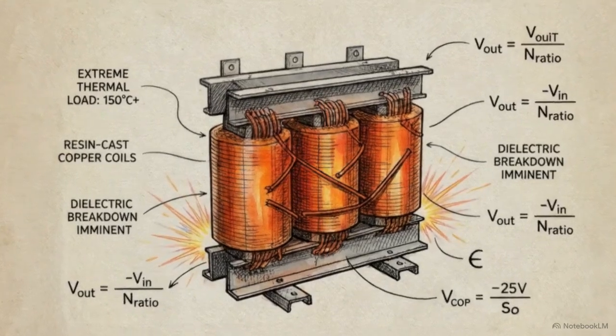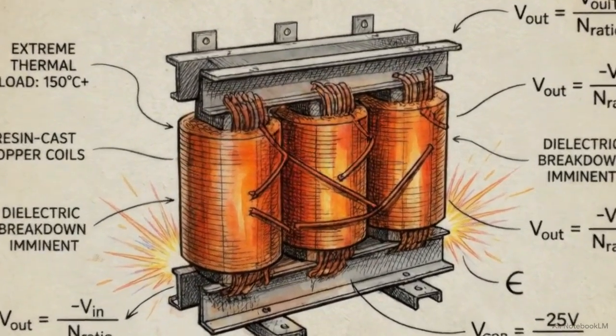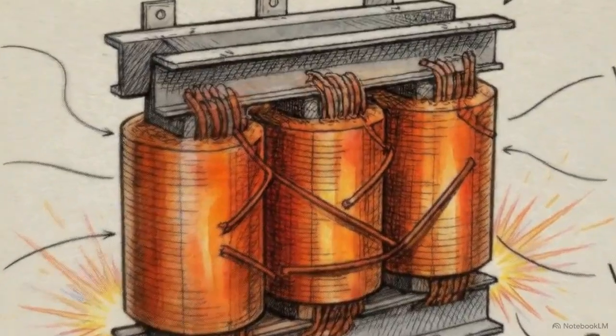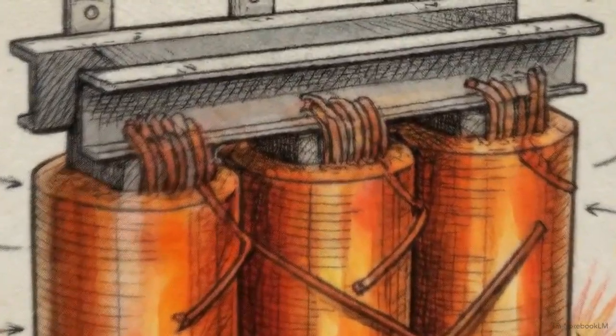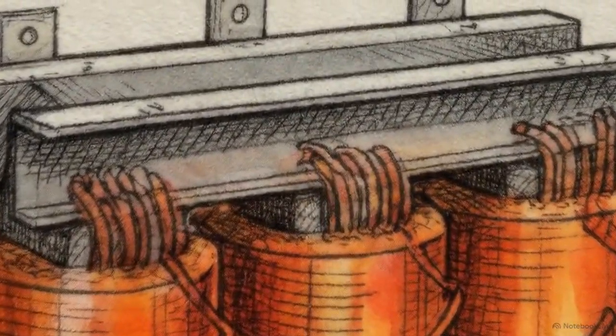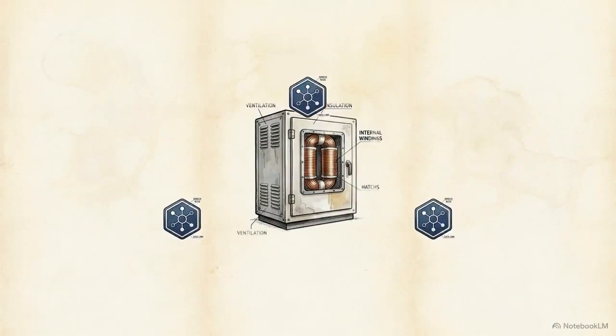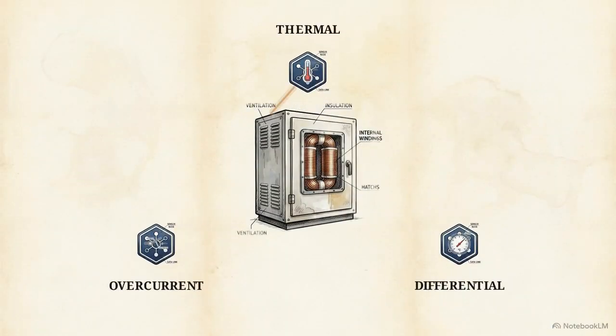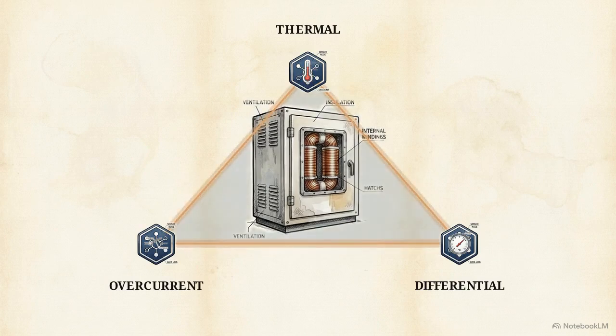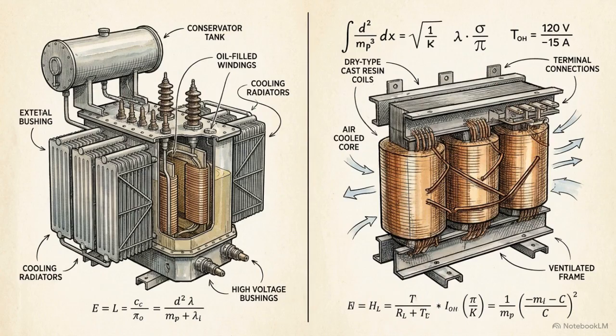Transformers are the silent workhorses of our power systems, but a sudden internal fault can turn an expensive industrial asset into scrap metal in seconds. To prevent that, we are going to configure a specialized 3-part protection protocol designed specifically for a dry-type transformer. This requires a different approach than traditional utility transformers.